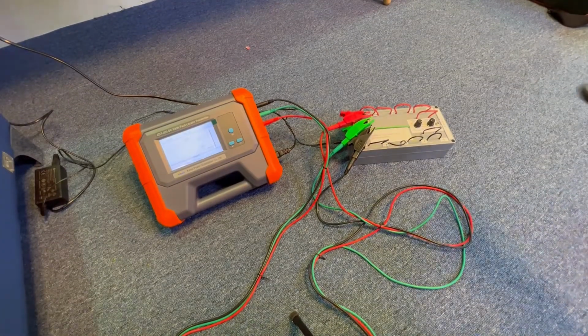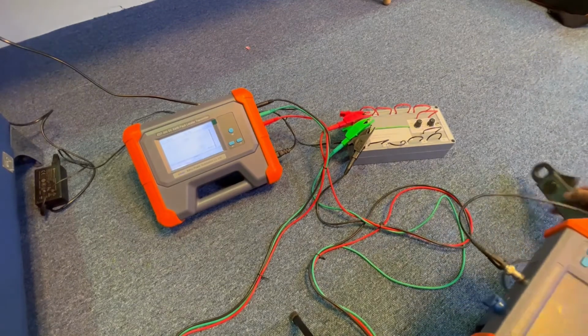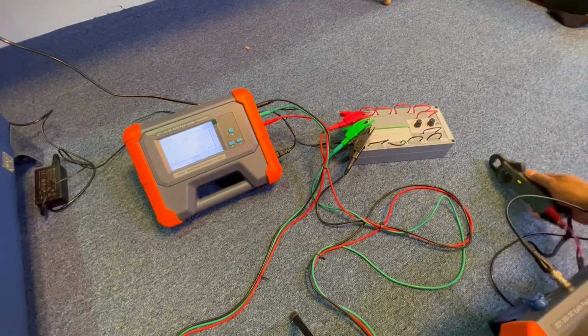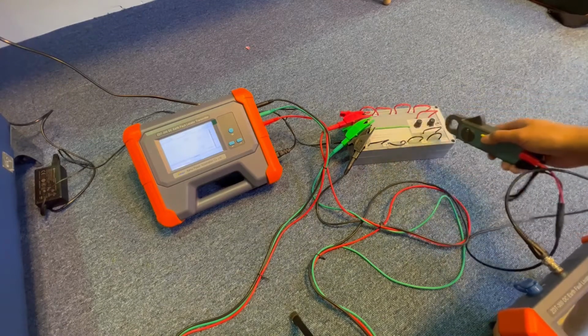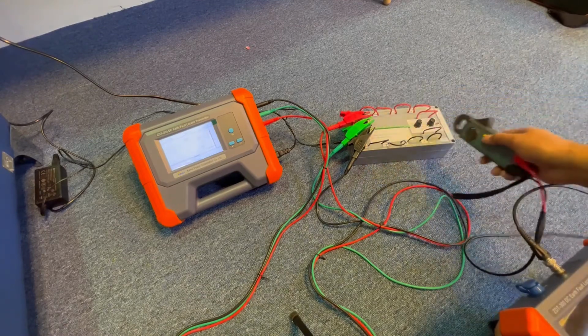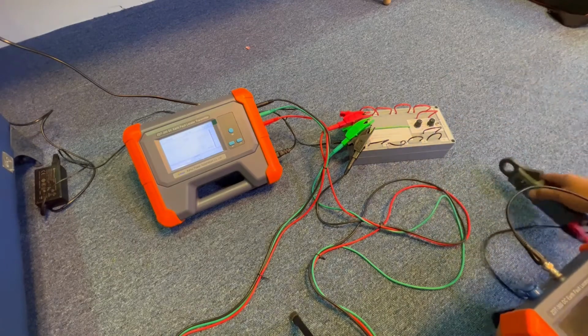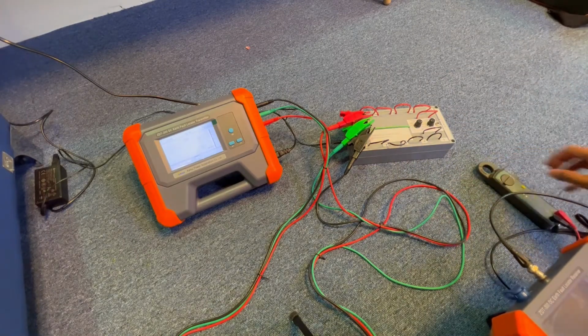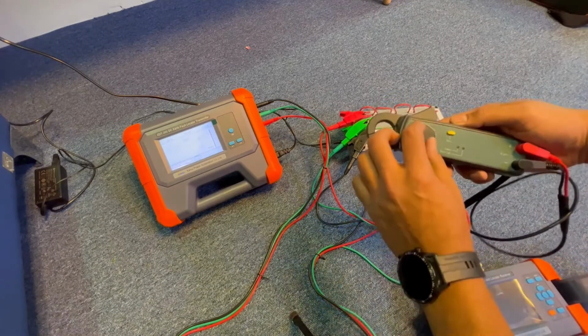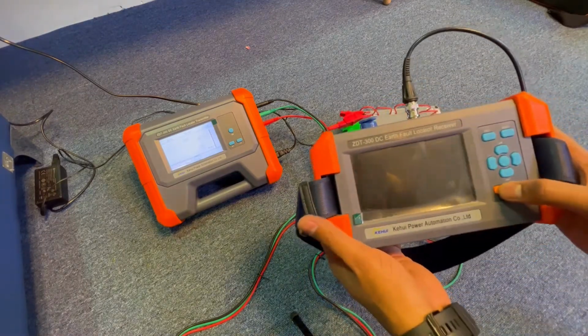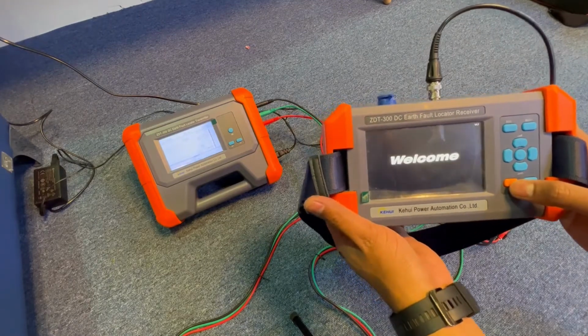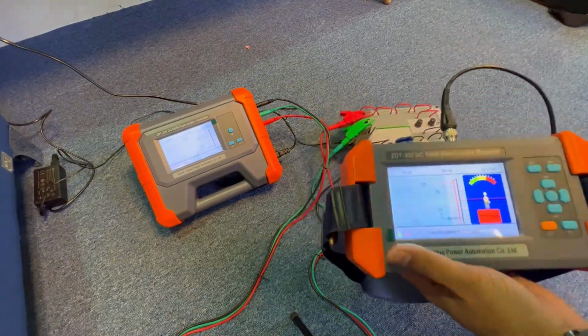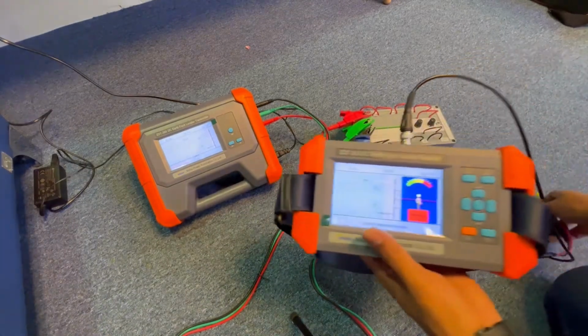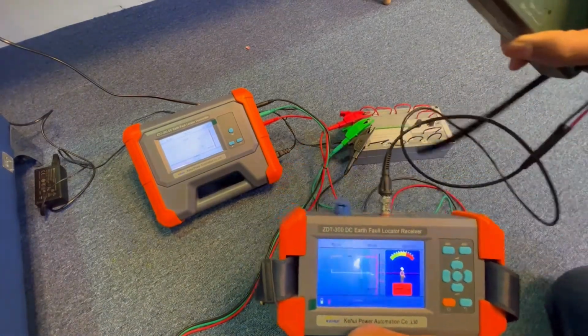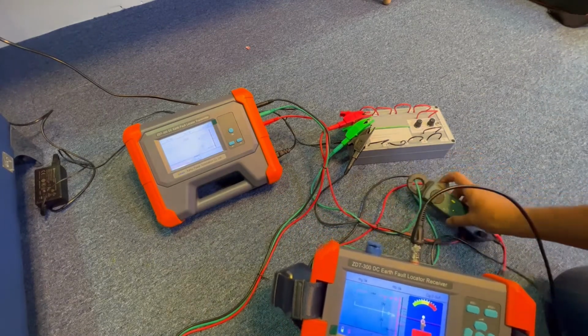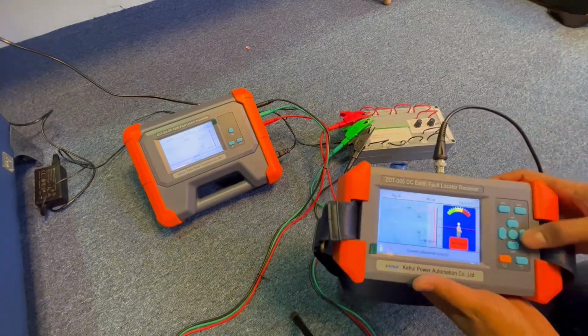So now we are starting our demonstration on healthy feeders first. We have to identify all the feeders' healthiness. Out of these feeders, any one feeder might be faulty based on the fault to ground condition. So we switch on this receiver clamp, then just press for 2 seconds. Your receiver will be on. Now you need to connect this receiver to the ground cable and see whether it is really grounded or not.